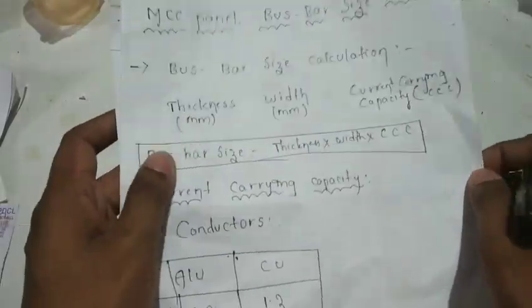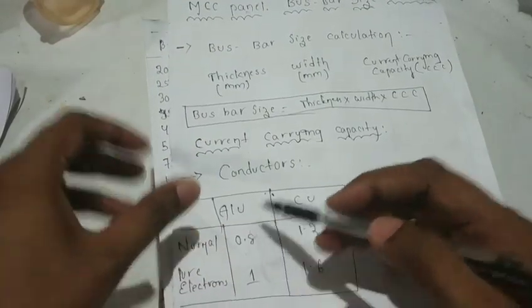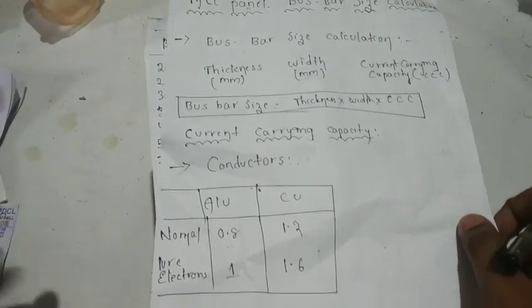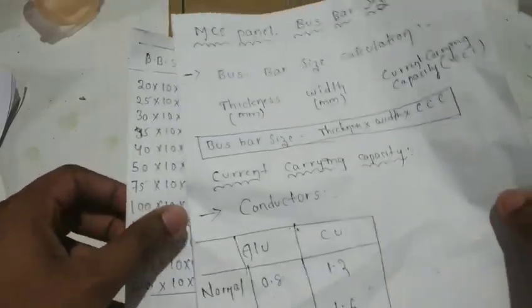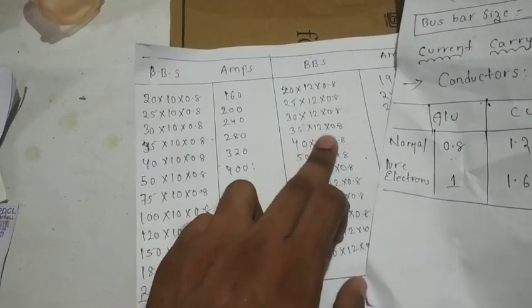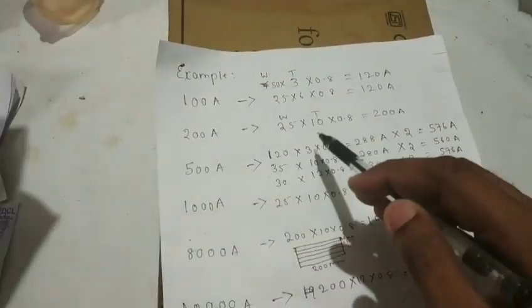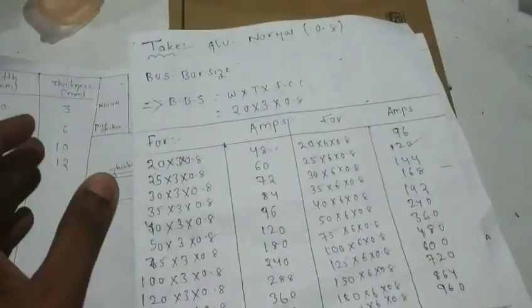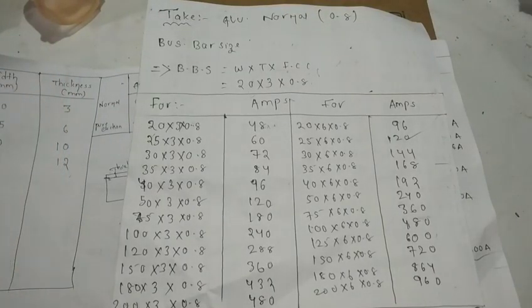So you can calculate the MCC panel bus bar. Aluminium bus bar uses a factor of 0.8. The formula is: multiply the thickness by the width by the current carrying capacity factor to get the bus bar current rating. Width times thickness times the current carrying factor gives the full load current amps. We will calculate the bus bar this way. If you like this video, please like, share, and subscribe.